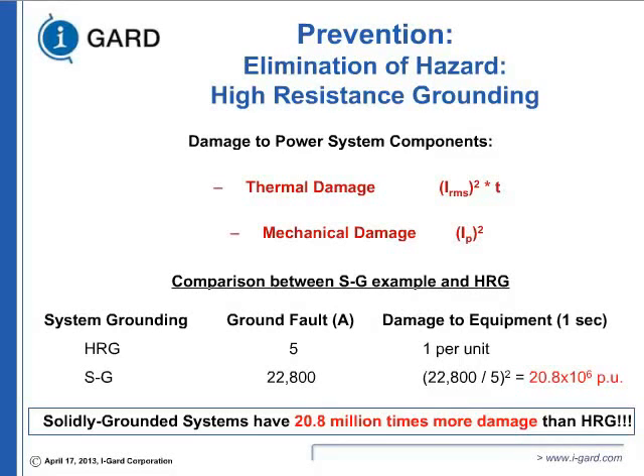That means on a high resistance grounding, you probably would not have any damage. On a solid grounded system, you will have a fire, you'll have a big explosion, and you have a potential of an incidental process fire or a person getting hurt.